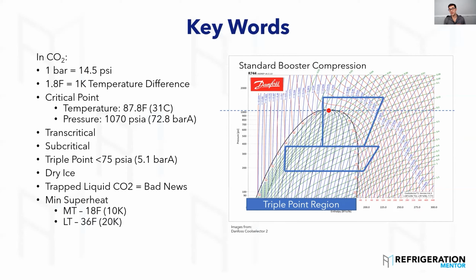And this is where I've seen many compressors fail, because a lot of people do not check compressor superheat. You should be really checking the compressor superheat on any system. Some people call it total superheat, some people call it system superheat. So you have your evaporator superheat, and then you have your compressor superheat. And it's so important to check that on any system at all. Always check that, because if you're running below that with CO2 systems, you're going to start to wear those bearings out, and you're going to cause a failure.